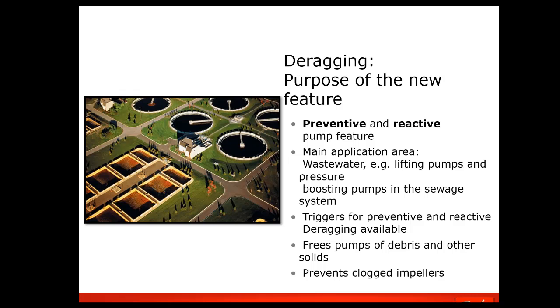The active function for declogging and keeping the pump impellers free. It can be used in a preventive mode that can be set to do the deragging feature or function every time the drive starts or stops. That is a selective function of the drive, or it can be reactive based on motor power, and that is a tunable item in the drive also.